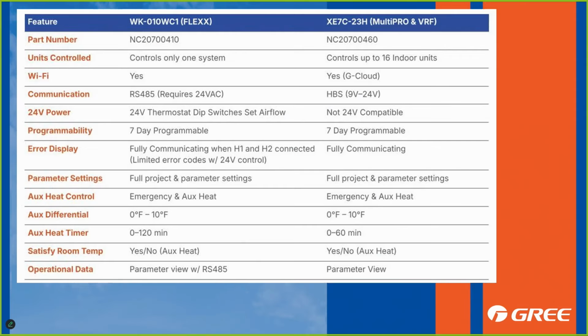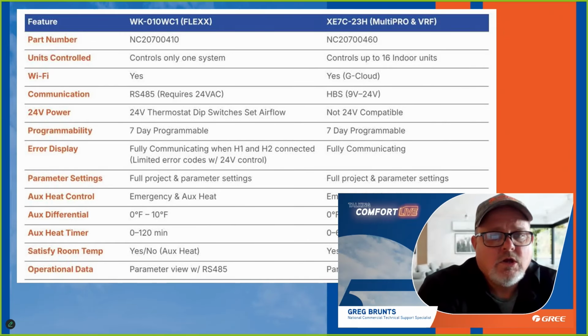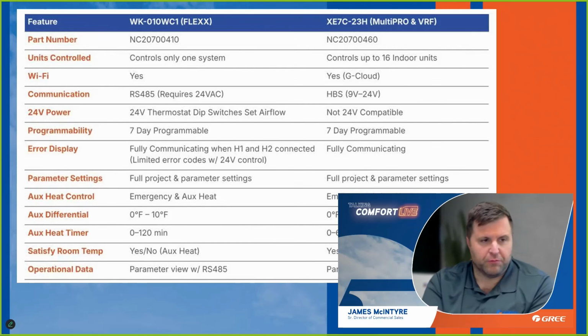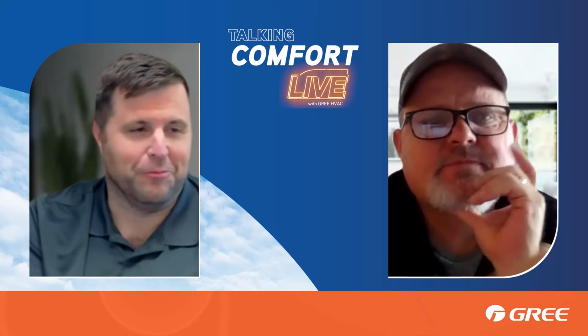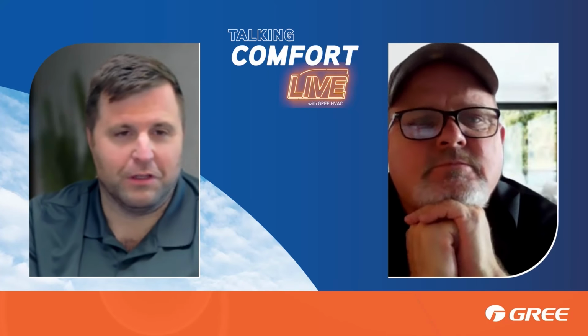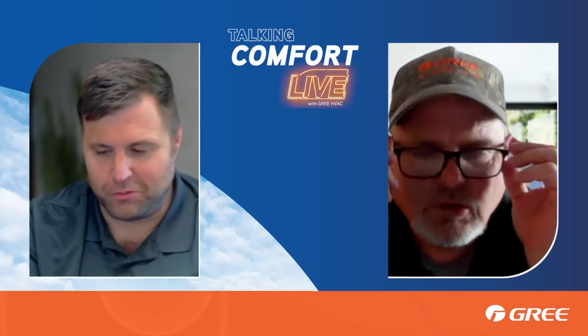So I can tell you right now, guys, at my house, mine's set at 60 minutes. I don't want that electric heat coming on unless it's been at least 60 minutes. Right. The big downside to that is that you're talking about a high efficiency system. The customer's buying a high efficiency system. They are planning on saving money on their energy bill, but their habits can offset whatever savings they may have had. If they're spending an hour or two using electric heat trying to catch up from the abnormally low set point that they set while they weren't at home or when they're asleep, for example, then they're using their full heat kit and also their heat pump at the same time trying to catch up.